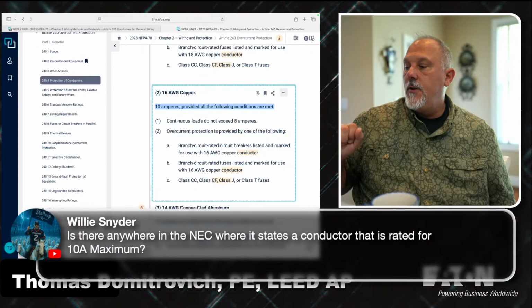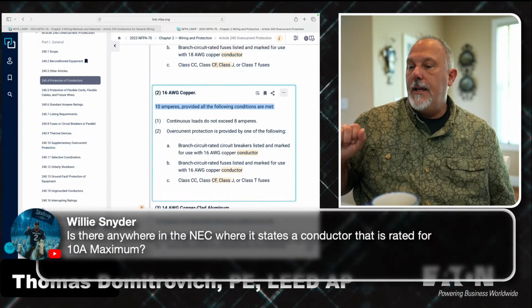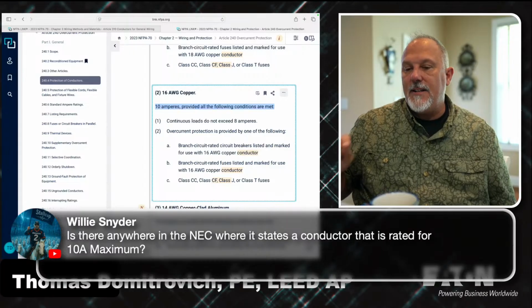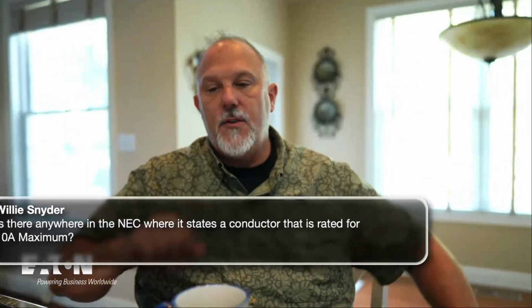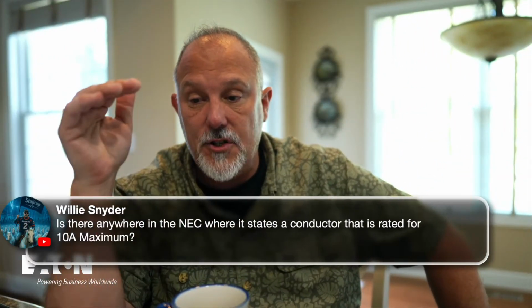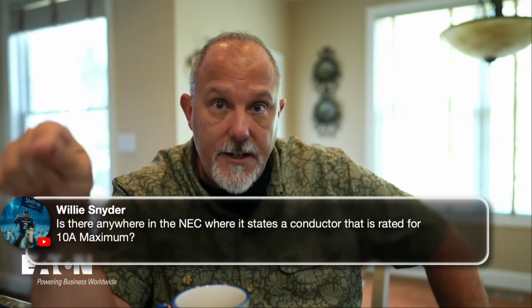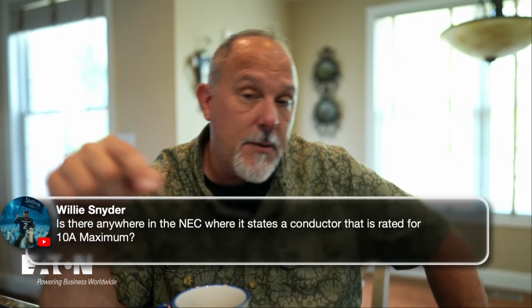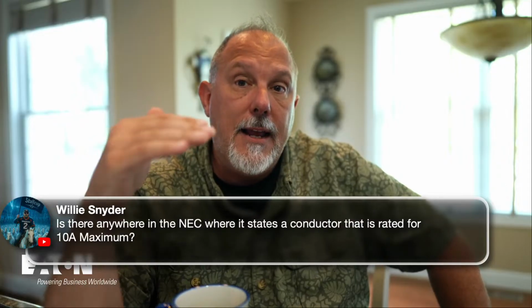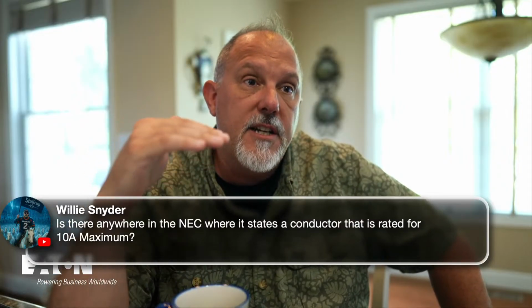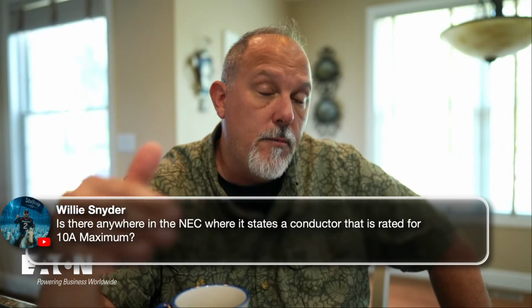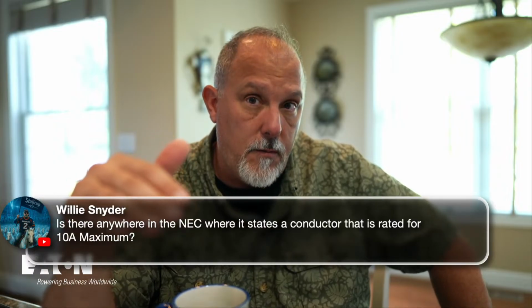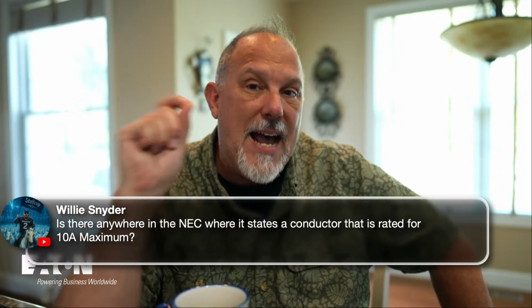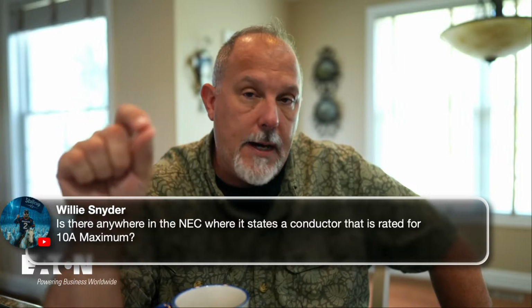So would I say that the NEC tells you that the conductor is rated for 10 amps? I would say no. Nowhere in the code does a conductor have a rating. We removed that a couple cycles ago. Conductors have ampacity, not a rating.